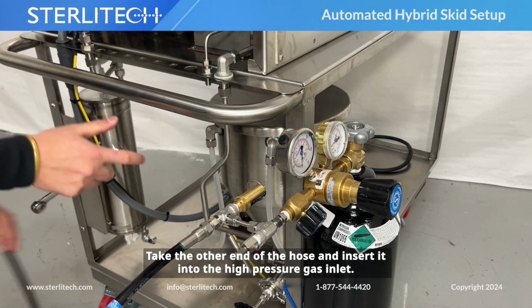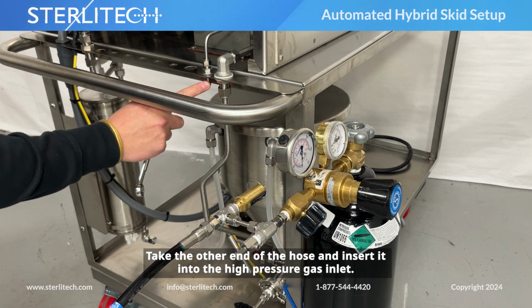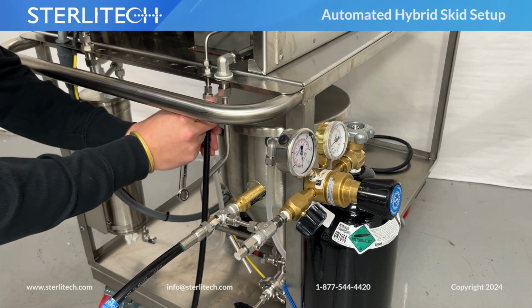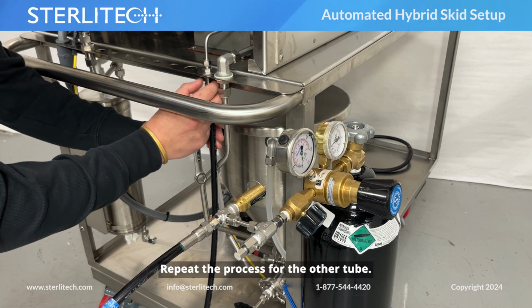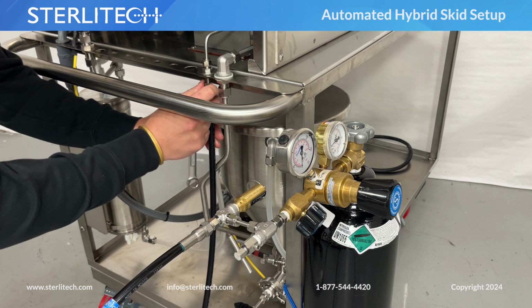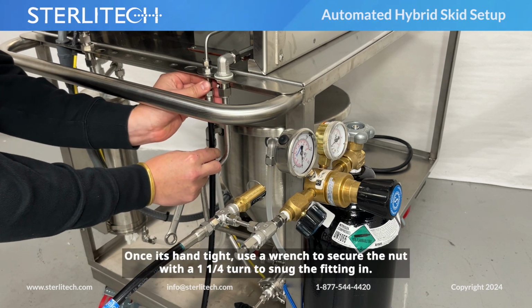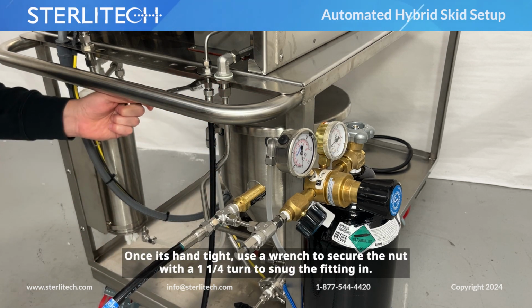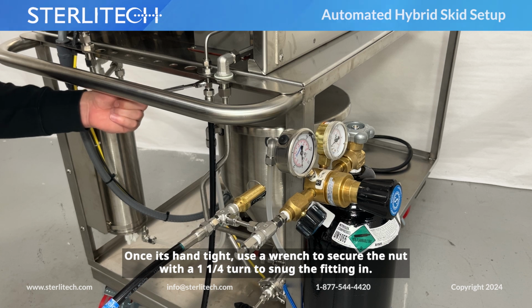Take the other end of the hose and insert it into the high-pressure gas inlet. Repeat the process for the other tube. Once it's hand tight, use a wrench to secure the nut with a 1 1/4 turn to snug the fitting in.